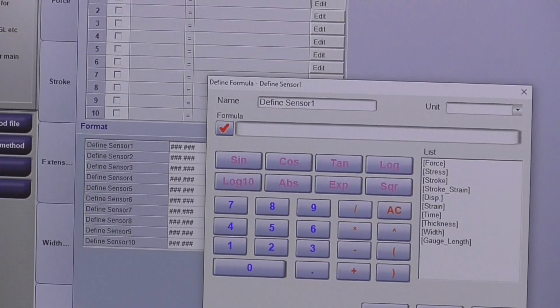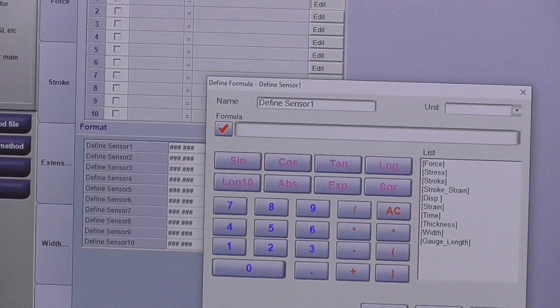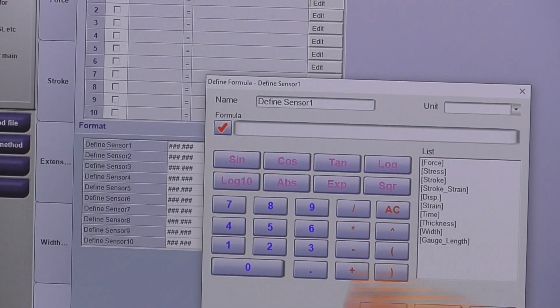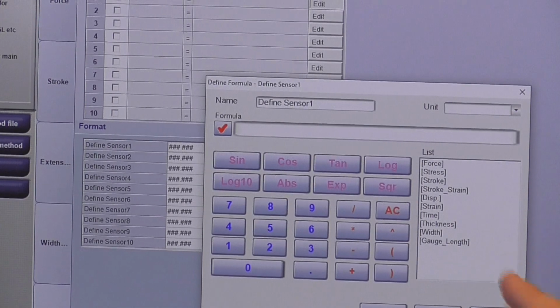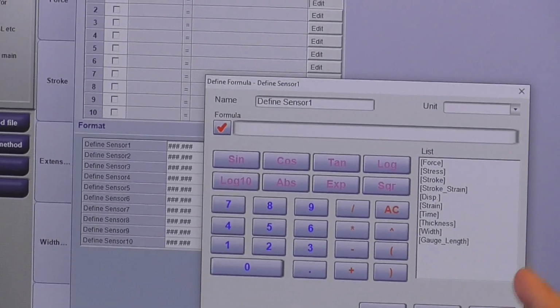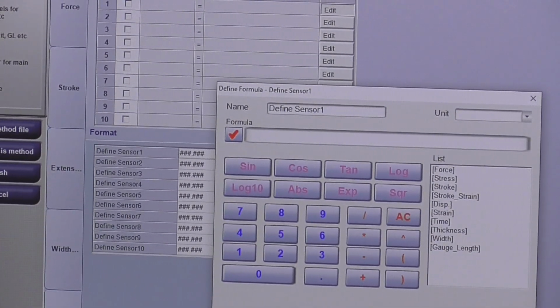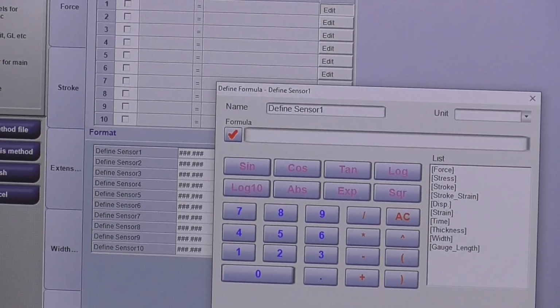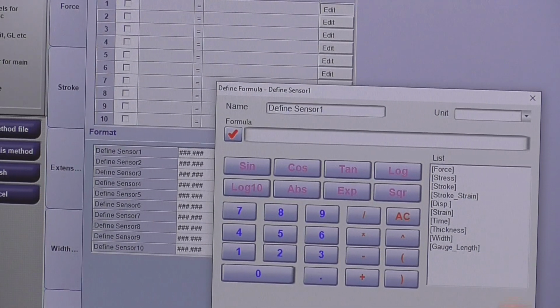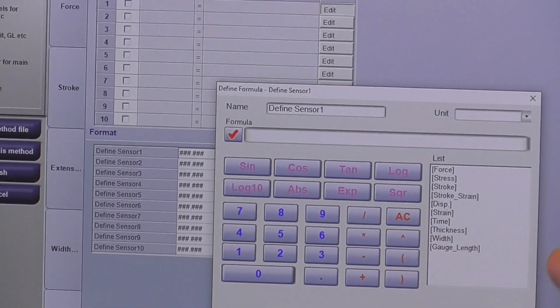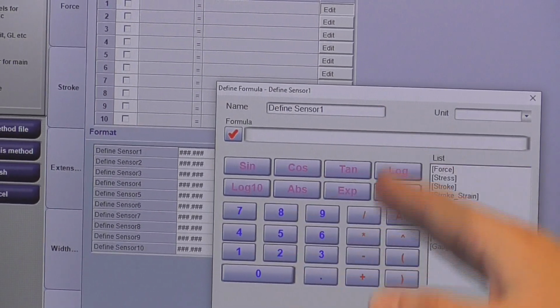And also, if you'd want to log those stress values or those strain values, you could do that through here as well. And when I say log, if you want to export the data, we do have a reporting function, but if you want to export the data into a CSV format, the only thing that you're going to export is those two data channels, your force and your displacement. If you wanted to export a strain channel, you would have to add that in here as well.